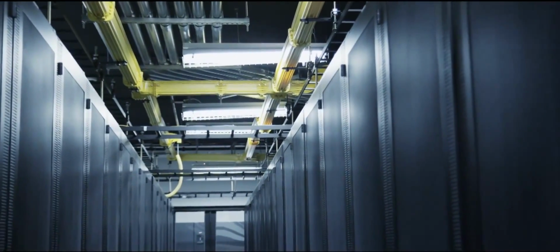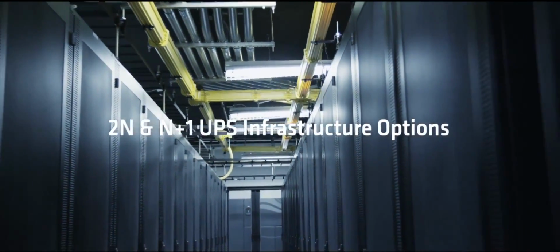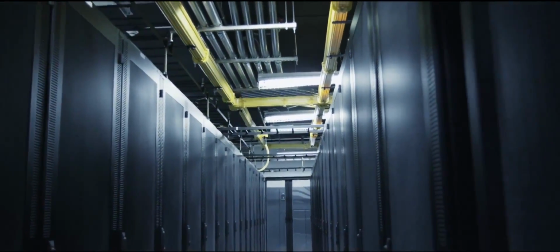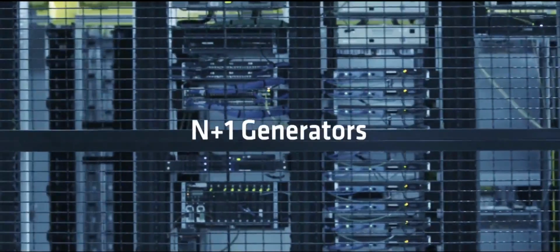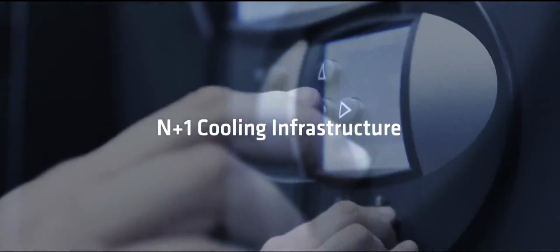Designed to support up to 175 watts per square foot or 6 kilowatts per cabinet, the facility allows for both 2N and N+1 UPS configuration options. Its power source is backed by an N+1 generator configuration. Efficient cooling is accomplished with an equally impressive N+1 cooling design.